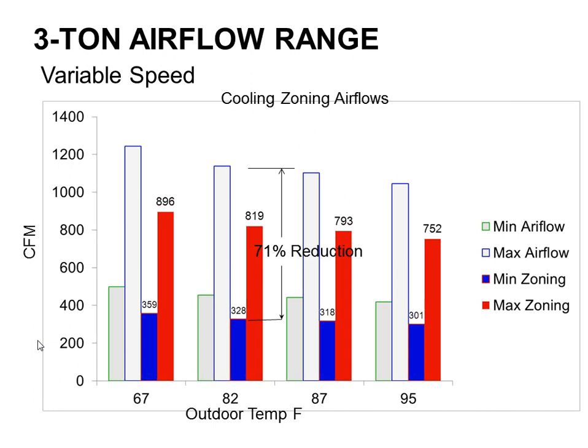How often can you take a 3-ton unit down to 300 CFM? You're basically running like a 1-ton unit when you've got one of the smaller zones calling for cooling by itself, or heating for that matter. So this guy is definitely the quote-unquote zoning unit.